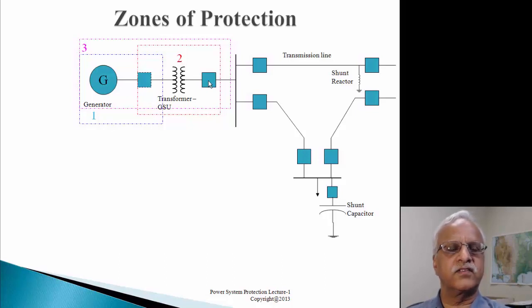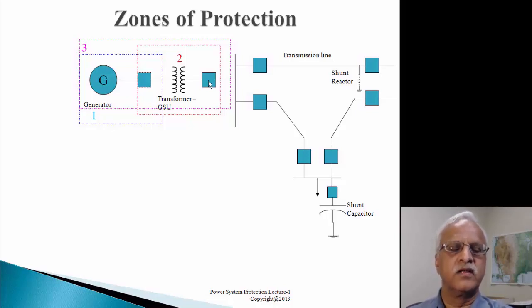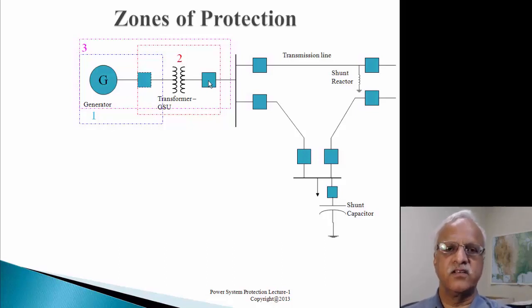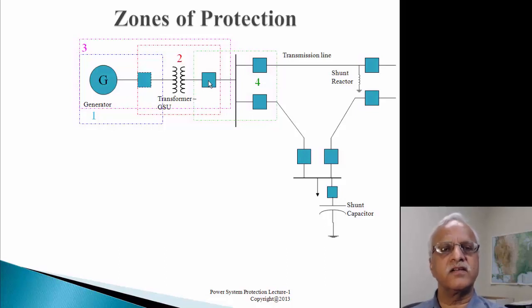If the size of the generator is very large, it is difficult to obtain a generator breaker. So generators are directly connected to a step-up transformer, with only one breaker on the high side. This connection is called unit connected generators, and this protection is called unit protection. For a bus - which is a junction of three or four equipment connections such as a generator and two transmission lines - we monitor the currents coming into and going out of the bus relay.